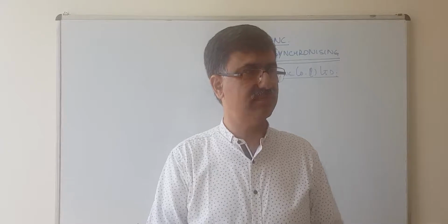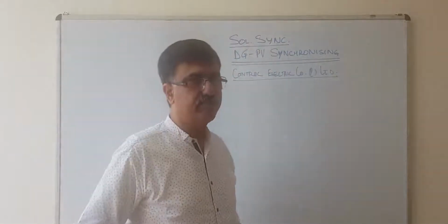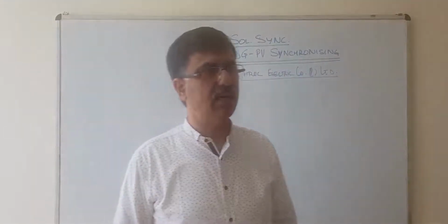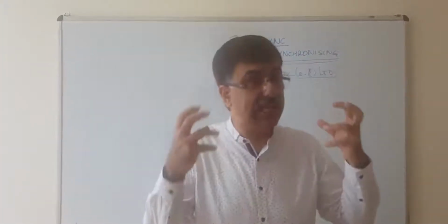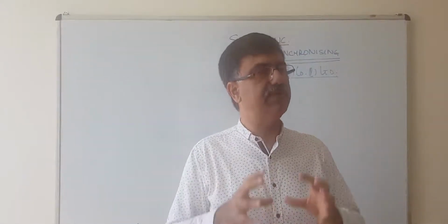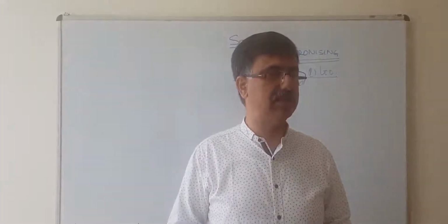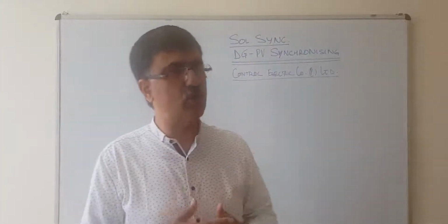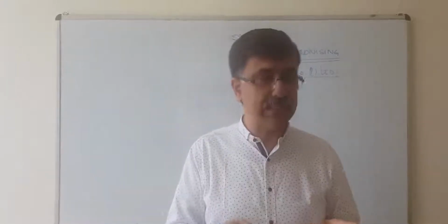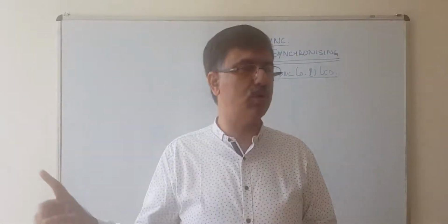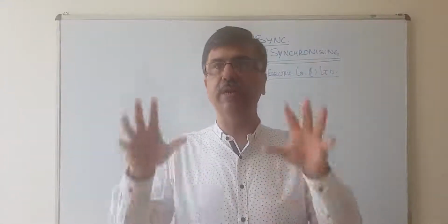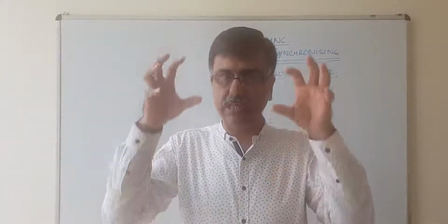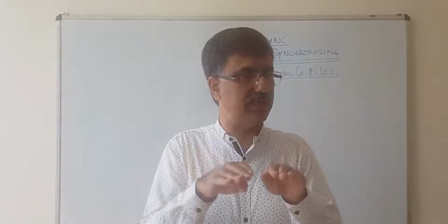Just this DGPV sync or SolSync or sleeving, they're one thing only, right? Yeah, these are different names that I use. Somebody will say it's a sleeving device. Somebody will say it's a power curtailment device. Somebody will say it's a synchronizing device. Whereas I'm making it clear, there is no synchronizing done by anybody. The solar inverter today has a built-in facility of synchronizing with the DG.